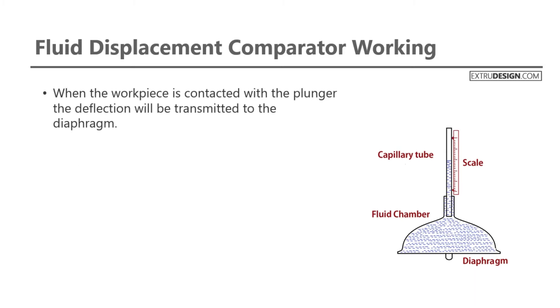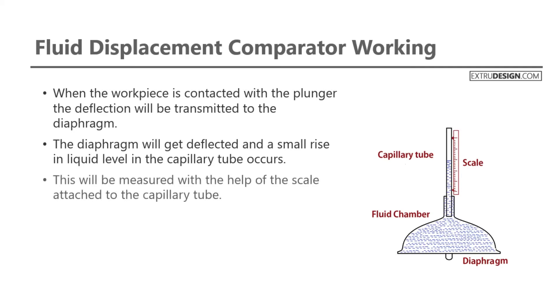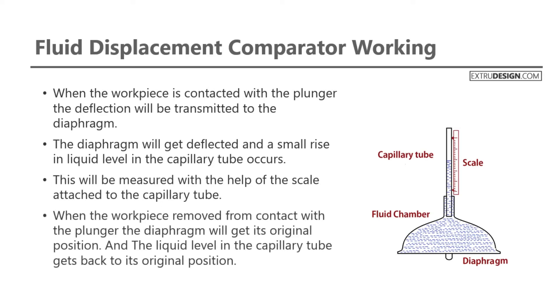When the workpiece is contacted with the plunger, the deflection will be transmitted to the diaphragm. The diaphragm will get deflected, and a small rise in liquid level in the capillary tube occurs. This will be measured with the help of the scale attached to the capillary tube. When the workpiece is removed from contact with the plunger, the diaphragm returns to its original position, and the liquid level in the capillary tube gets back to its original position as well.